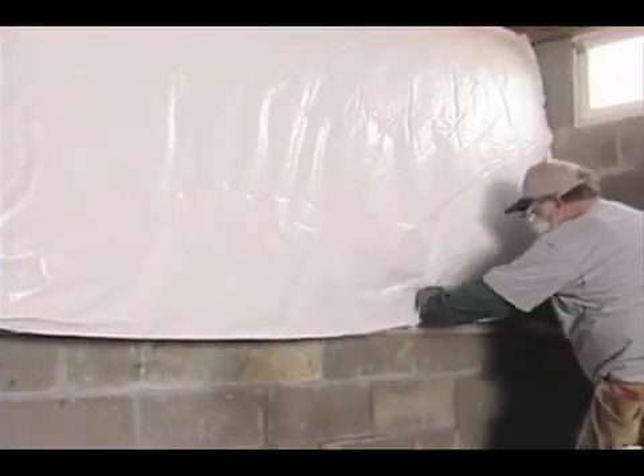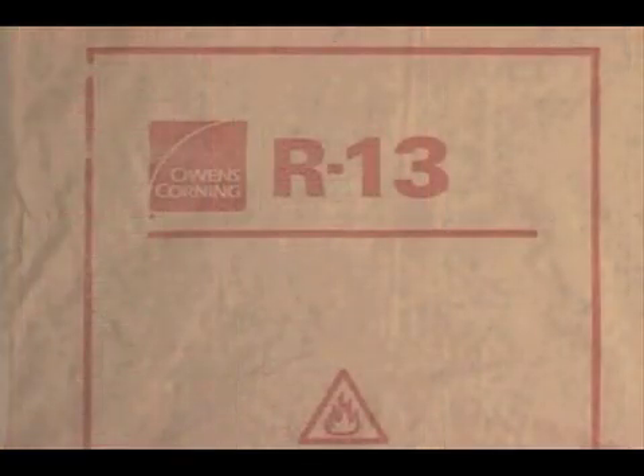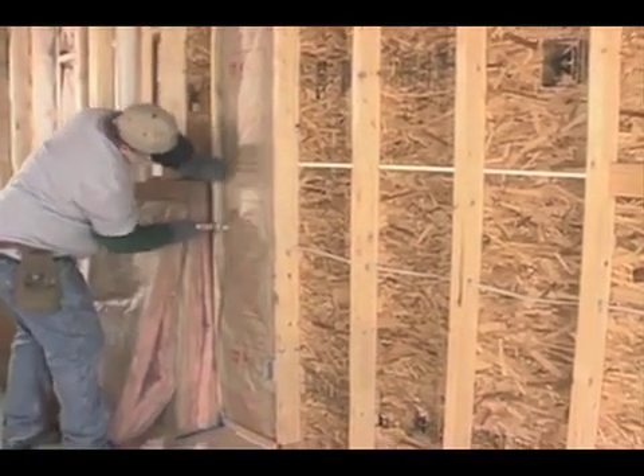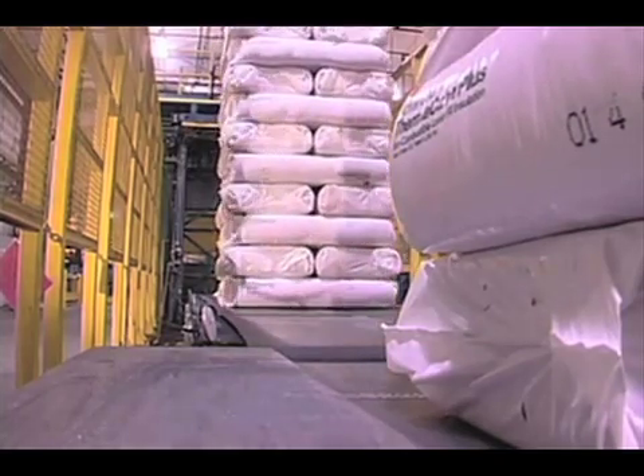A secondary function of the facing is to provide a protective covering when the application will be left exposed — for example, a basement blanket. Note that standard kraft paper and foil facings are combustible and cannot be left exposed. They are marked with a warning statement and must be installed in substantial contact with an approved ignition barrier, such as gypsum wallboard. The facing is usually attached to the insulation with a light coating of asphalt or a very thin layer of polyethylene, which melts during the curing process. Fiberglass loose fill insulators are produced in either bonded form, where the glass fibers are held together by a resinous glue or binder, or unbonded, where no binder is required.